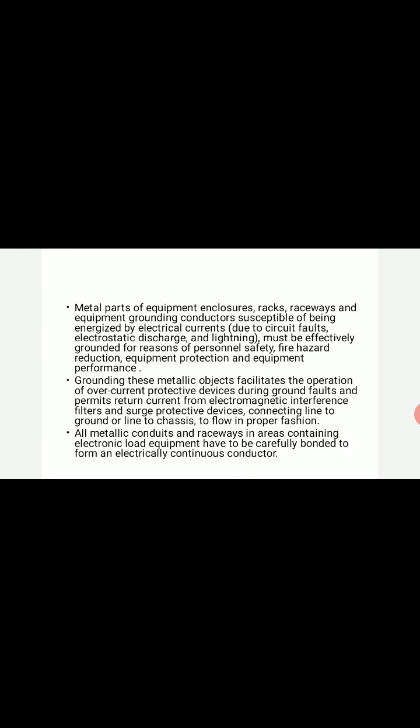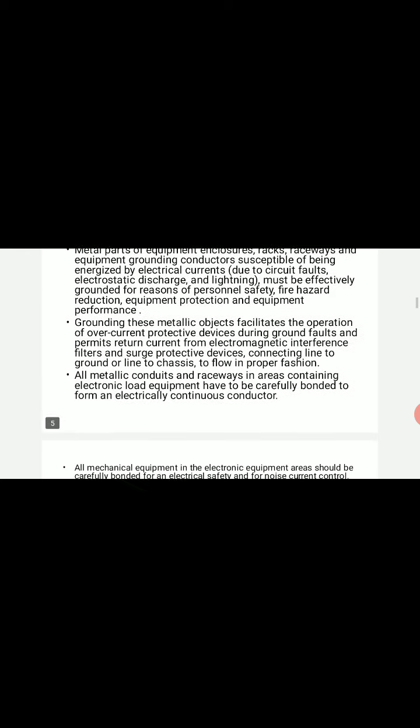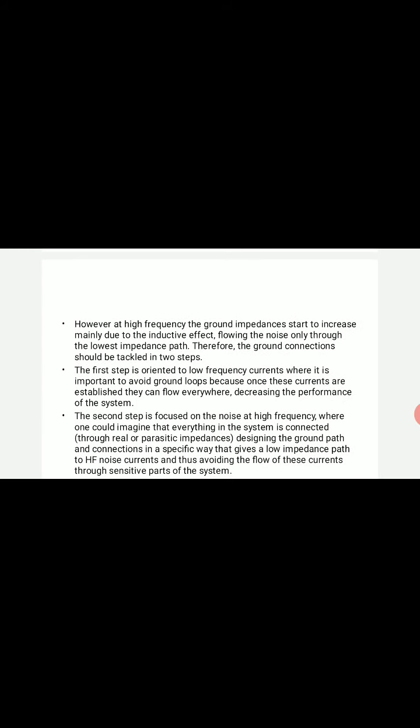Metal parts of equipment enclosures, racks, raceways, and equipment grounding conductors susceptible of being energized by electric currents must be effectively grounded. Grounding these metallic objects facilitates operation of overcurrent protective devices whenever ground faults occur, and permits return current from electromagnetic interference filters and surge protective devices connecting line-to-ground or line-to-chassis to flow properly. All mechanical equipment in the electronic equipment area should be carefully bonded for electrical safety and noise current control.